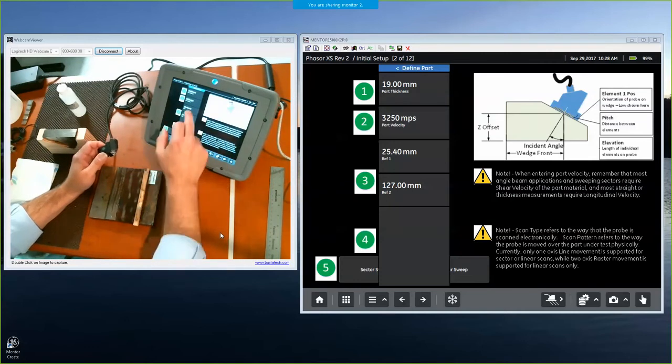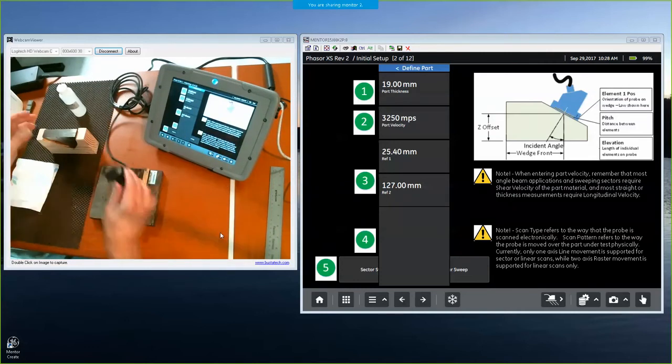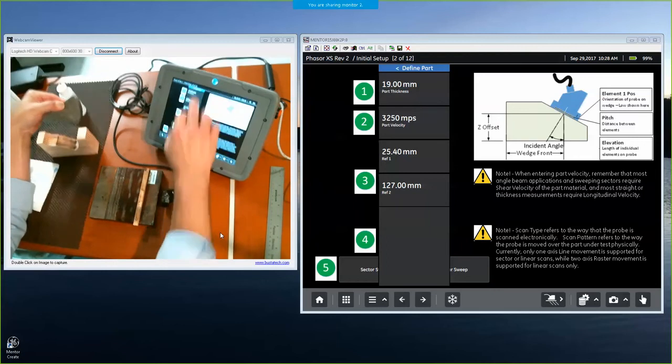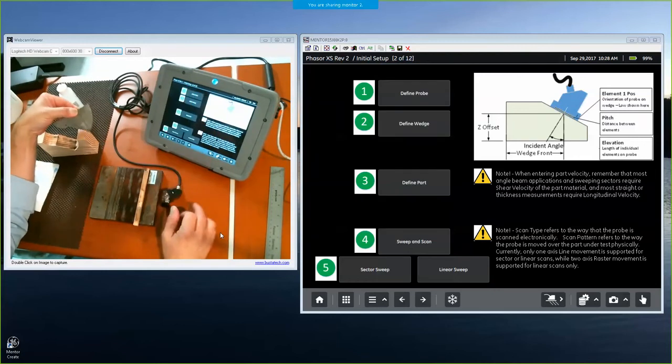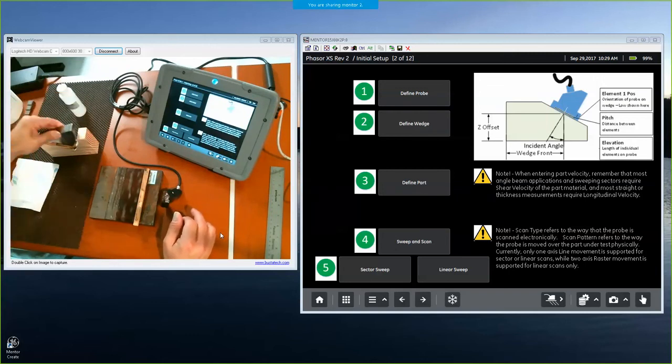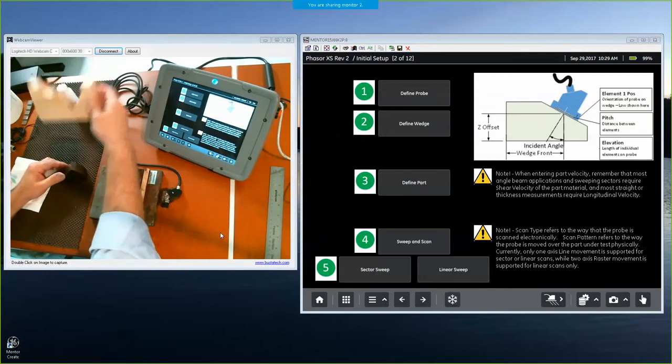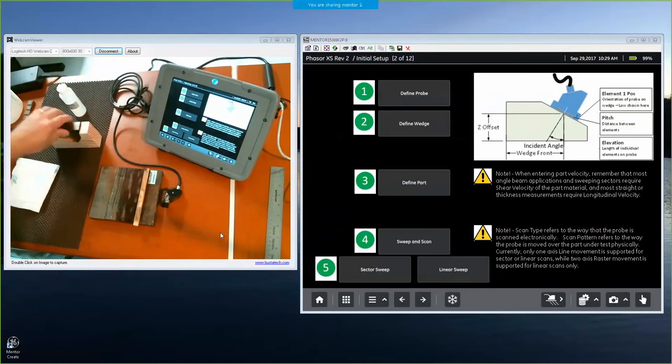And the ref 1 and ref 2 are distances that we're going to use in our calibration block for different steps of the calibration. I built this app mainly around the DSC test block because it's a nice size to carry with you when you're going out to do demos and so on. I found it to be a bit of a pain to work with the DSC block because it never wants to sit nice on the desk. So I cut a little holder out of a scrap of 2x that I had laying around.